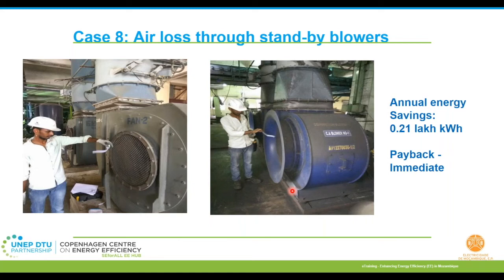The only fundamental problem here was they forgot to close a damper for the non-operational blower. So this way you are losing air, which means your operating fan is actually working slightly more to deliver the required air to the user side. So the simple operation was to close or minimize the opening of this damper, and they were able to save about 0.2 lakh units per annum.